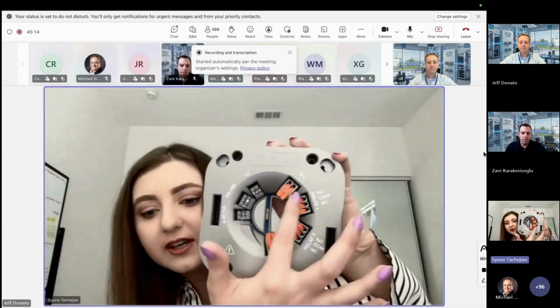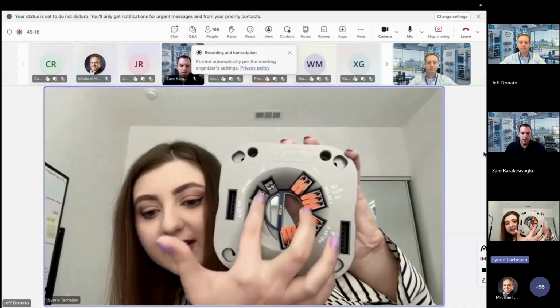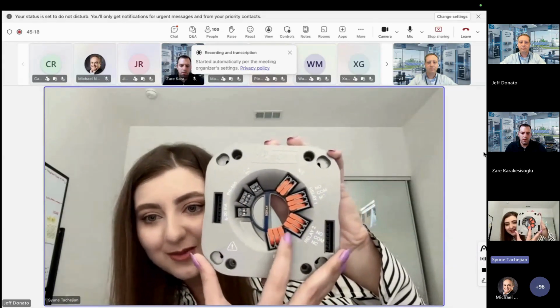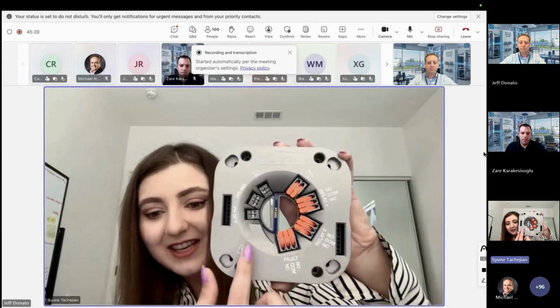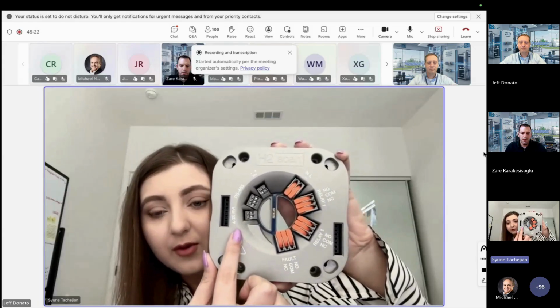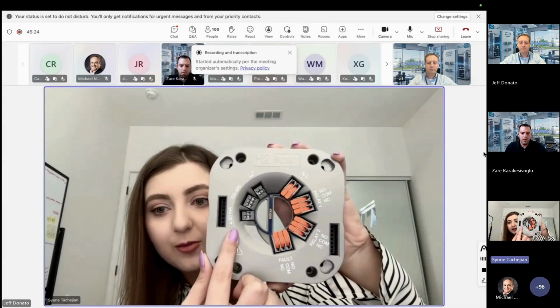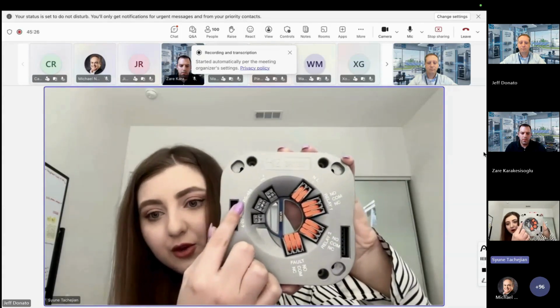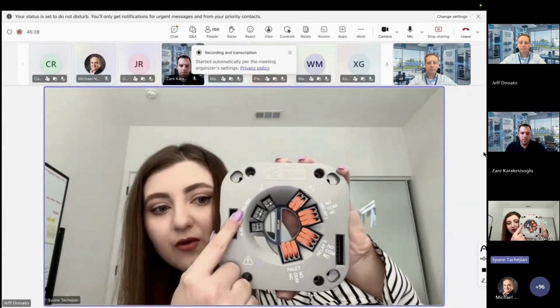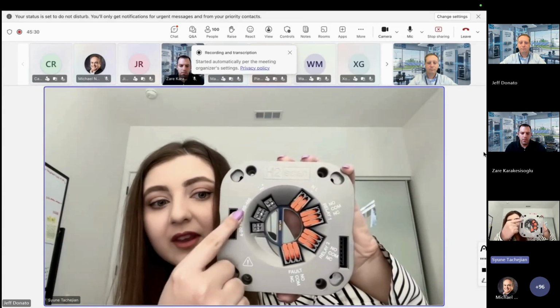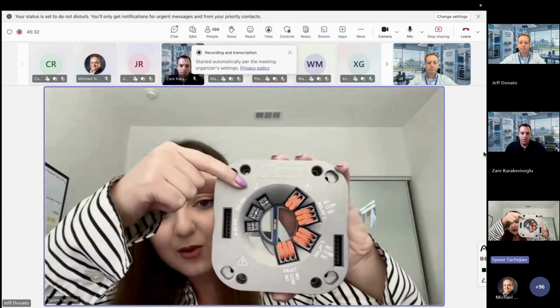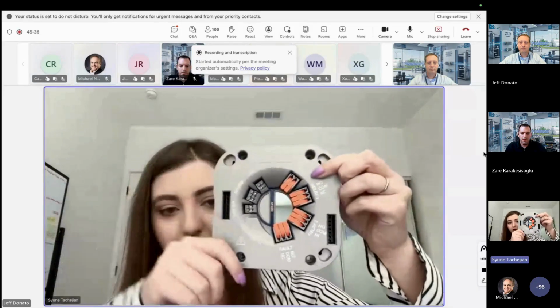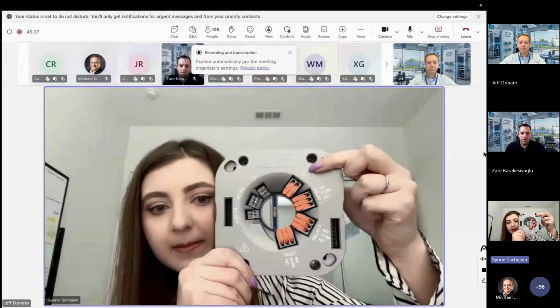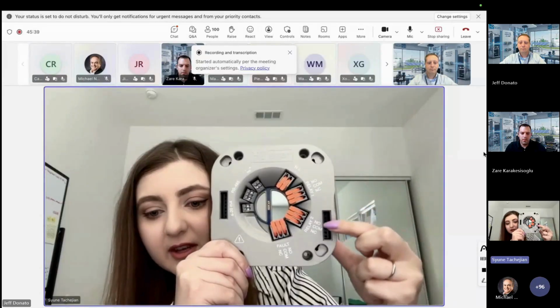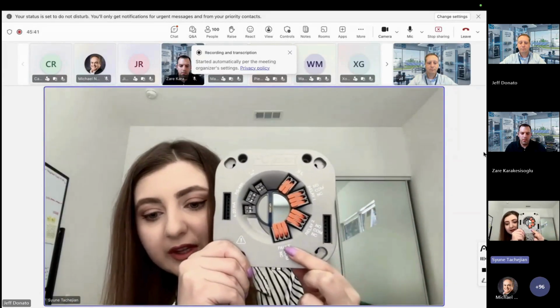Here is where you would wire into your connectors, just as you would on a Nest thermostat. Here you've got your 4 to 20 milliamp analog output. Here you've got your Modbus RTU over RS-485. Here you've got your DC power. On the other side, you've got your AC power, and then your 1%, 2%, and fault relays.